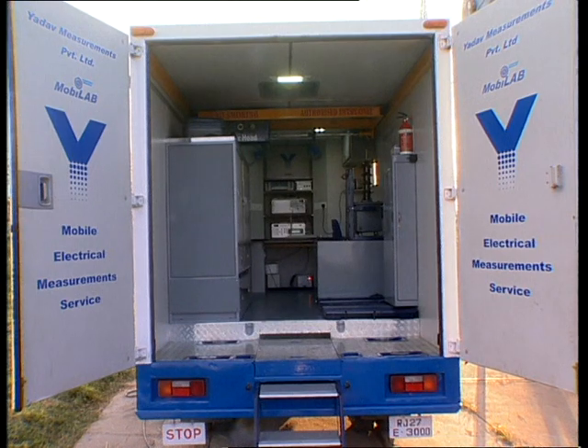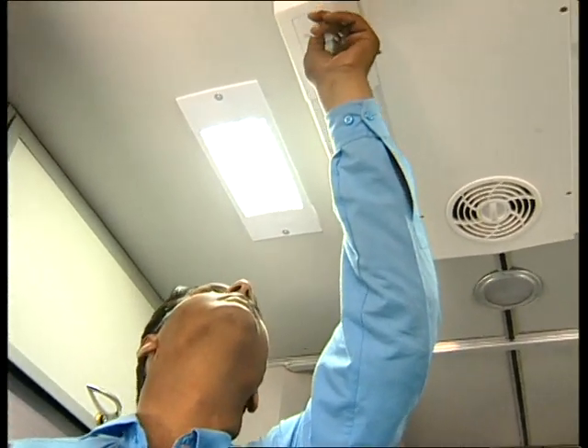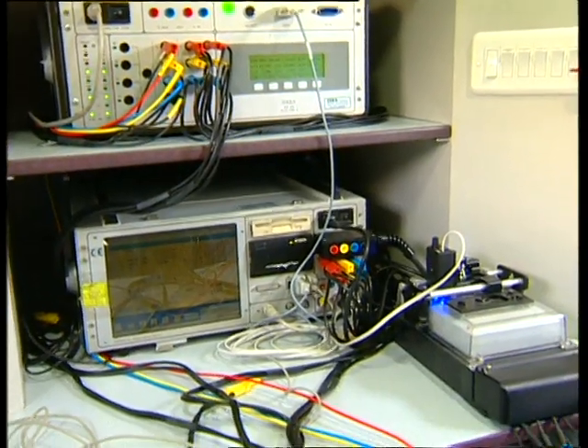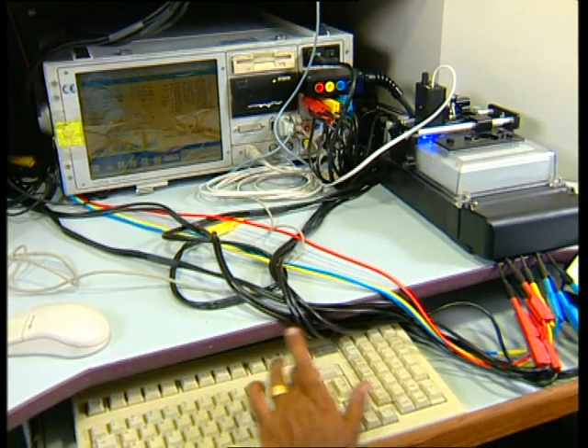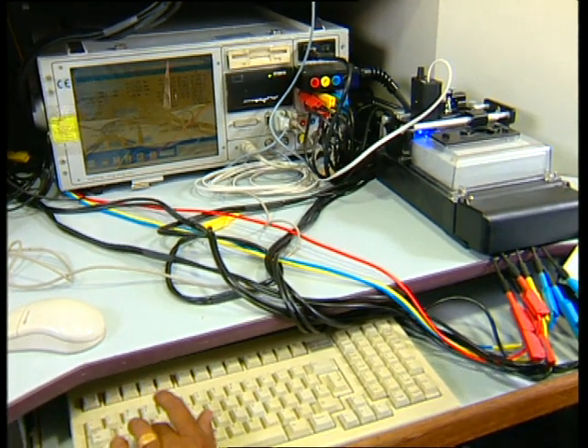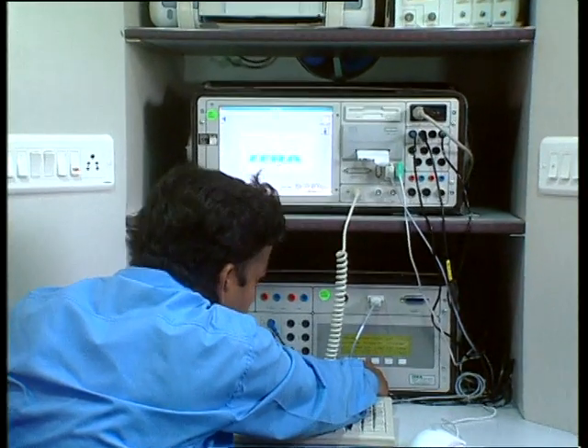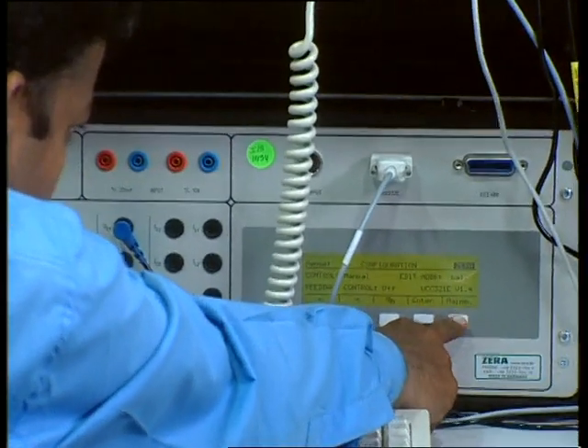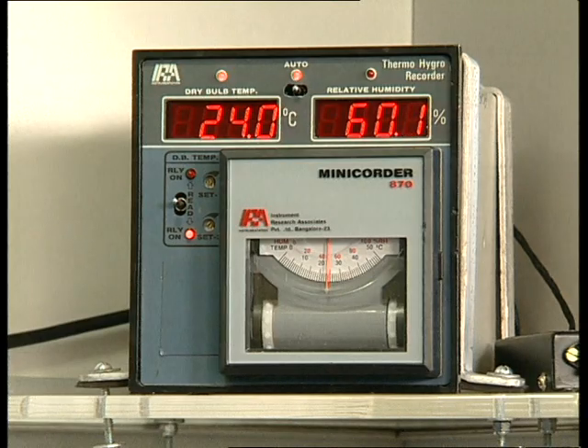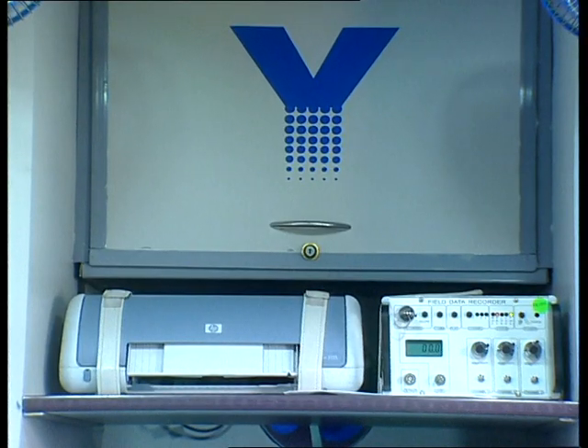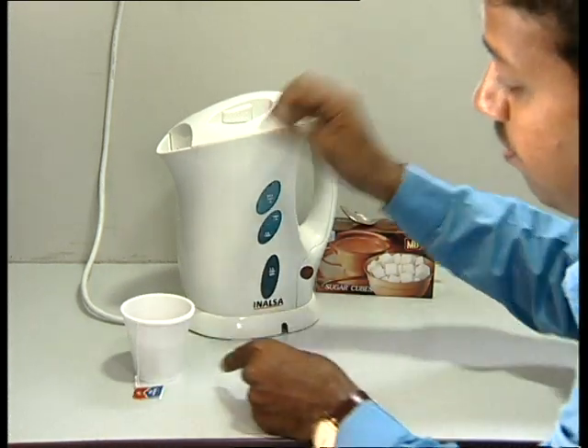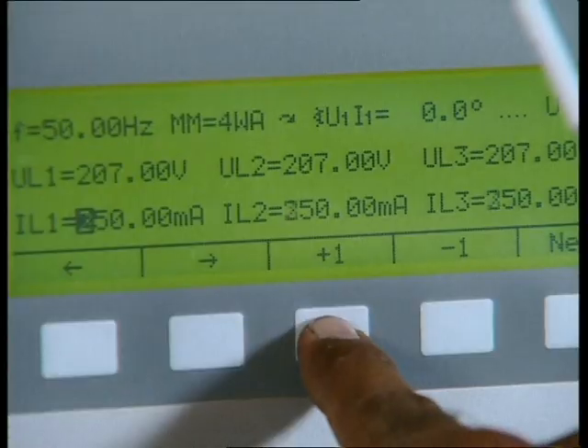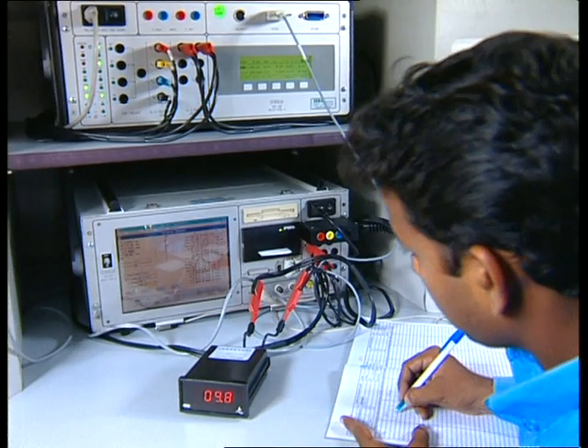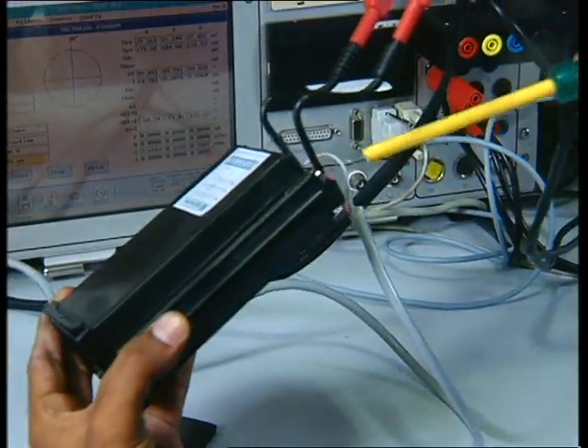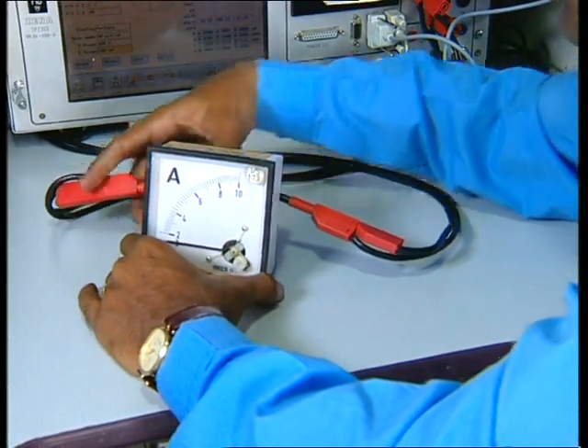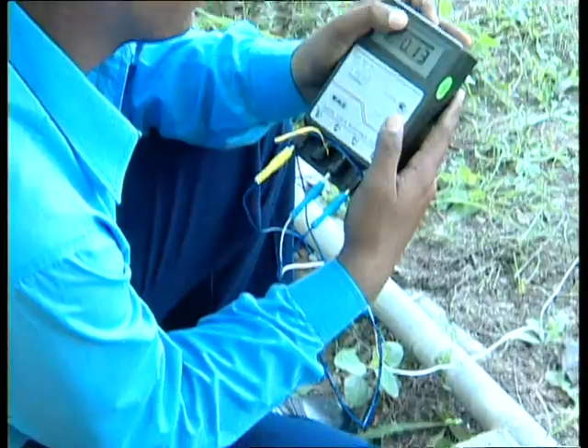Meters and indicating instruments are calibrated in the controlled environment of the air-conditioned interior of MOBILAB. MOBILAB is equipped with a precision energy and power reference standard of 0.02% accuracy, a measurement capability at least 10 times better than the most accurate meter in the substation. The tests are carried out using stable laboratory-grade static voltage and current source. The whole ensemble brings the capabilities of a second echelon laboratory to the substation, a facility never before demonstrated. Apart from testing instrument transformers and meters, MOBILAB can also calibrate other substation measuring instruments such as voltmeters, ammeters, power factor meters and frequency meters. Earth resistance measurements can also be carried out if needed.